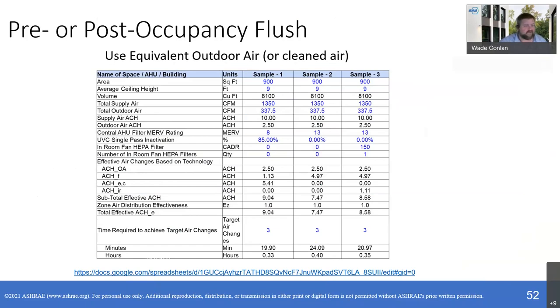And if I add an in-room unit, I can get to higher, right? Now, in Lindsay's talk, she was talking about 5 or 6 and what the target is, and that's for that classroom. But that information hasn't necessarily been updated for the Delta variant. So in any event, this could be for more of an ESE room or somewhere where you're not going to have masks or other things of that nature.